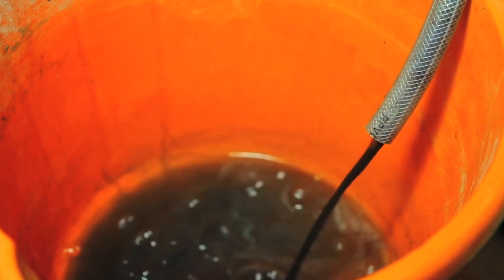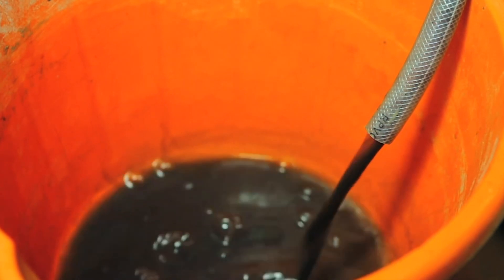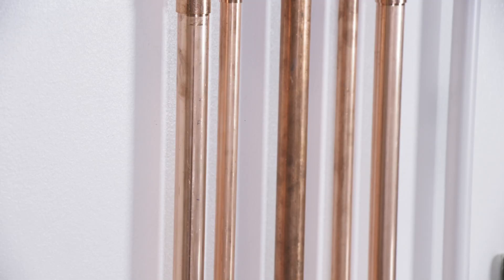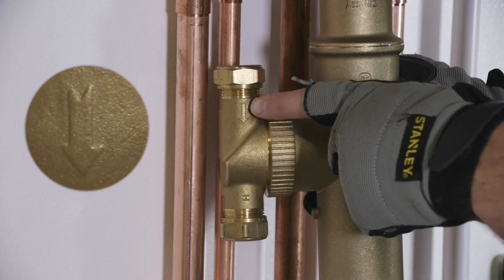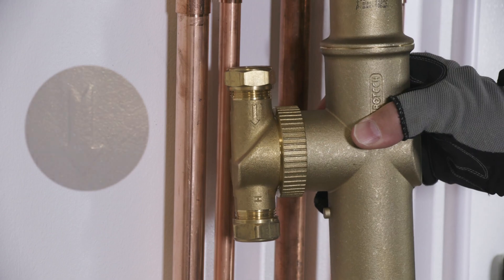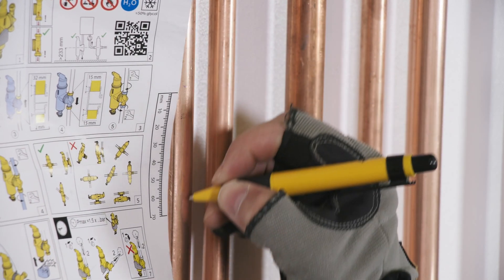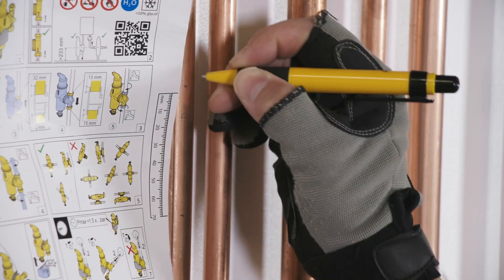To begin, drain the system and check that the pipework is suitable for the SpiroCombi MB3 to be installed. Locate the arrow on the unit which shows the direction the water needs to flow. To fit the SpiroCombi MB3 you will need a 70mm gap — there's a measure provided in the pack should you need it.